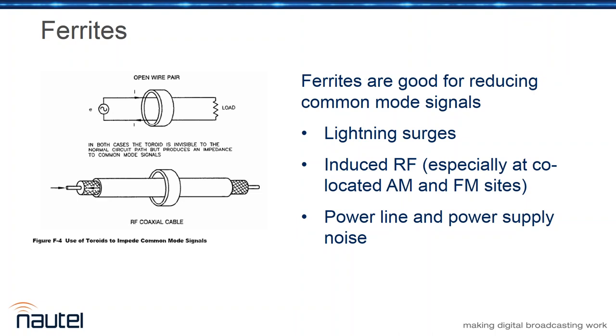The great thing about ferrites for common mode signals, for lightning for example, is that if you have equal feed and return currents, so your current coming in and your current going out are equal, the ferrite's an inert lump and totally invisible. But if you have a surge on one or the other, the ferrite will saturate and attempt to induce a surge so that the potential difference between the two stays the same. So ferrites are anywhere where you've got a feed and a return in the same cable set, whether it's AC wiring with three phases going out and a safety ground coming back, or a neutral, whether it's coax where you've got the feed in the center conductor and the return on the shield, whether it's shielded audio cable, anywhere where you've got the feed and the return in the same cable, the ferrite is a really good way of protecting against a common mode surge.